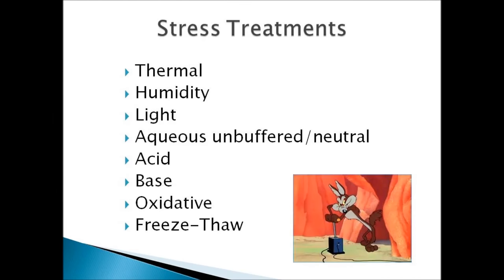Here is a list of stress treatments: thermal, humidity, light, aqueous unbuffered or neutral, acid-base, oxidative, and freeze-thaw. The top three generally are covered with solid samples or as-is materials, and the lower part generally pertains to solutions or suspensions. However, you can cross over as needed.